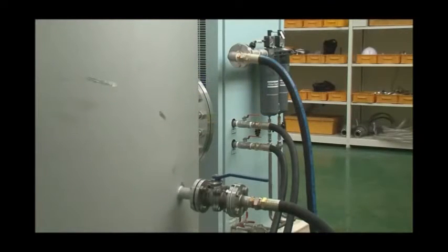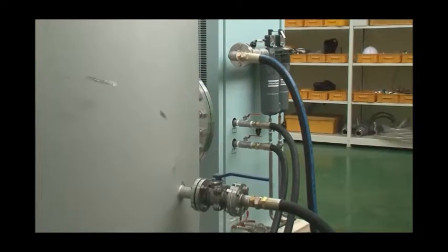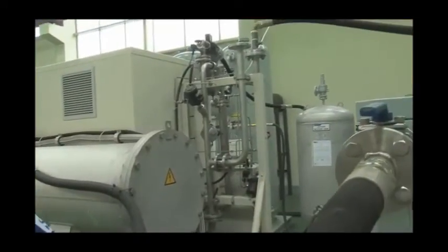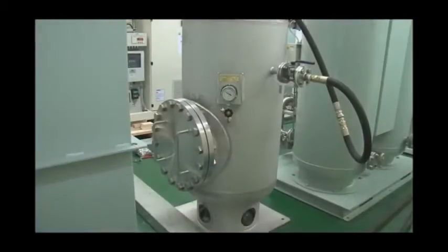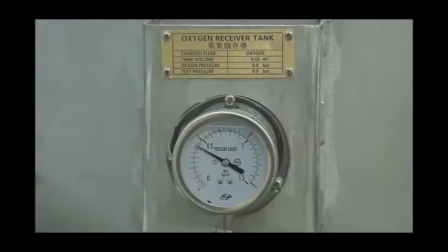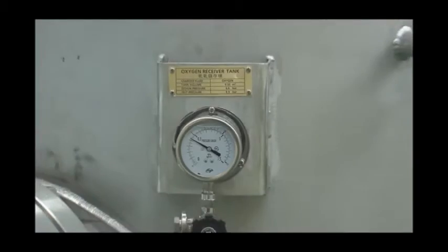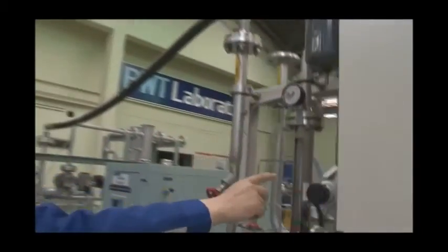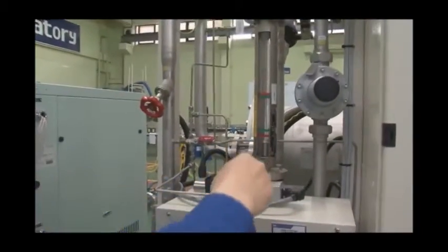It is recommended to use stainless steel material for air and oxygen receiver and also the connection pipes to keep air and oxygen in high quality. The produced oxygen from oxygen generator is stored in this oxygen receiver in between 4.2 to 4.6 bar, which contributes reduction of pulsation from the oxygen generator and stabilized oxygen flow to the ozone generator.